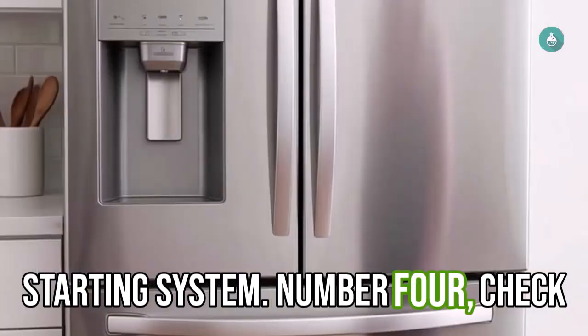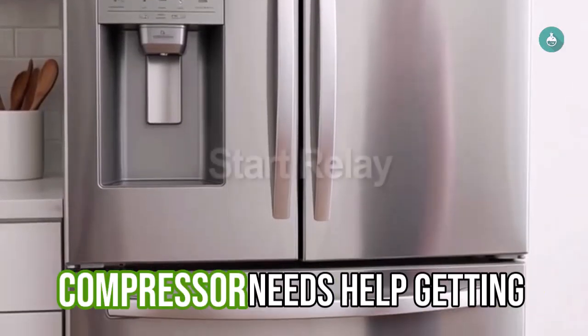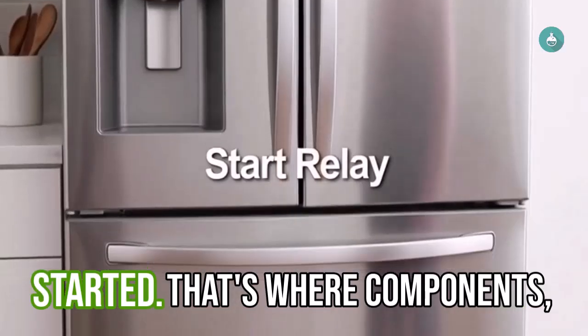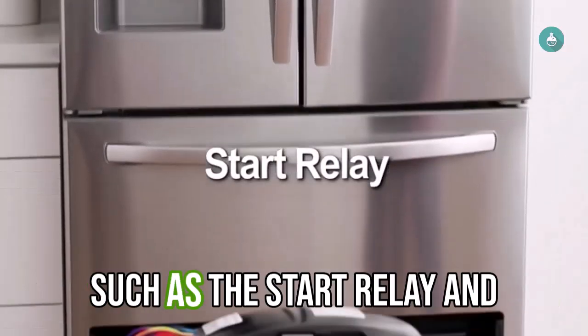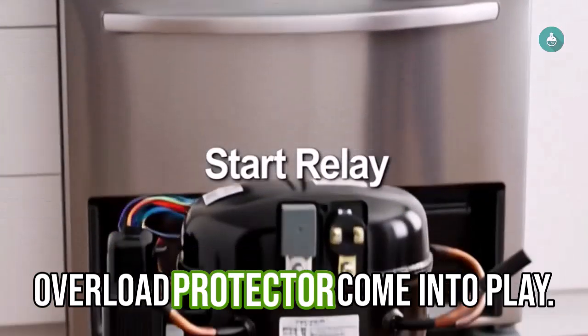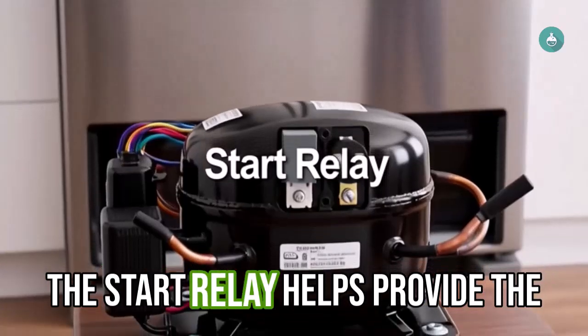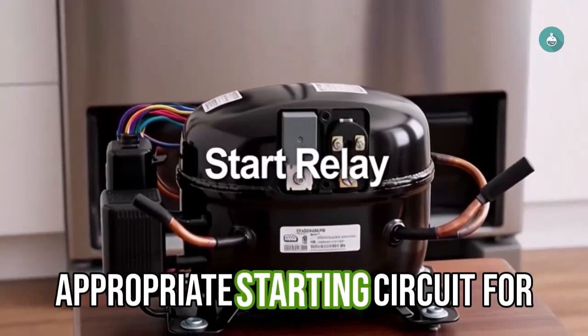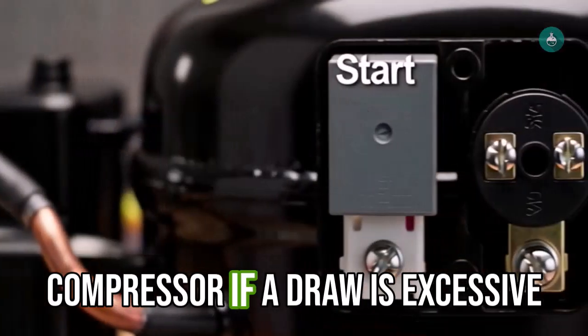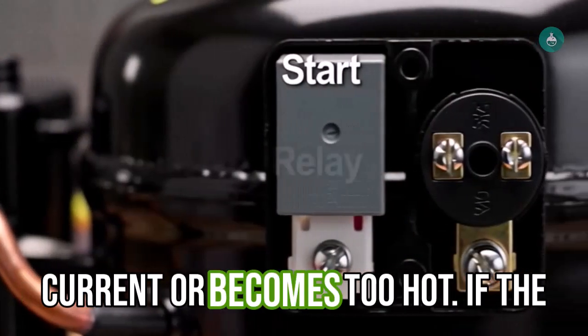Number 4, check the start relay and overload. The compressor needs help getting started. That's where components, such as the start relay and overload protector, come into play. The start relay helps provide the appropriate starting circuit for the compressor. The overload protector helps protect the compressor if it draws excessive current or becomes too hot.